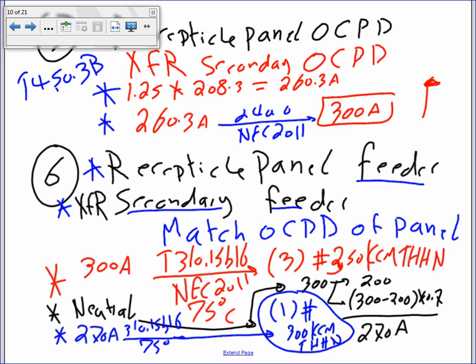Now, if your panel was a 400 amp panel, let me tell you what we do in real life. They don't go higher than a 225 amp receptacle panel. If the load is more, we just put another panel. We separate the panels. The reason for not having a receptacle panel too large is that you're putting too many eggs in one basket, number one, and voltage drop becomes an issue. When we design a receptacle panel, we take the whole building and start cutting it into sections. We have a 225 amp receptacle panel in this section, another section, a fourth section, and we made an engineering decision not to go more than 225 amp. And we pull full neutral, and everybody's happy.